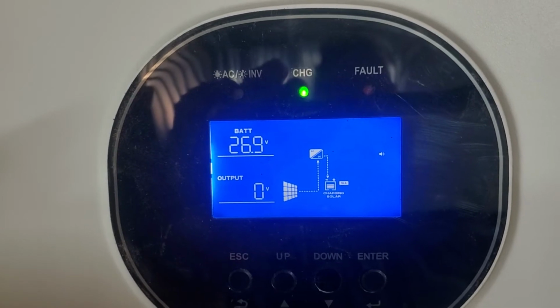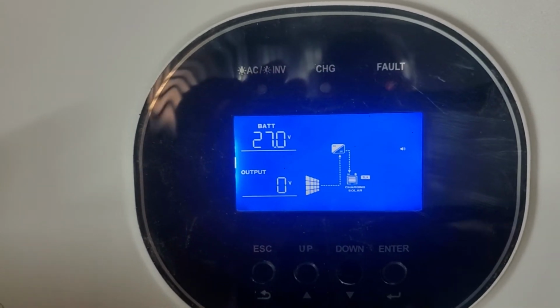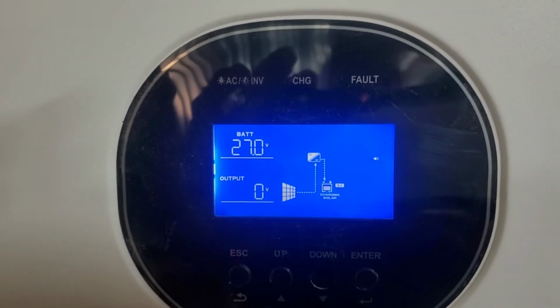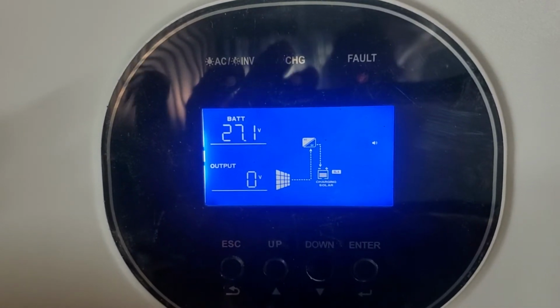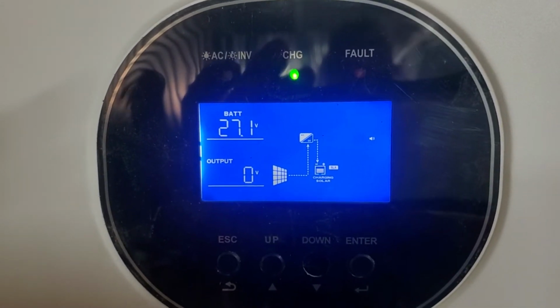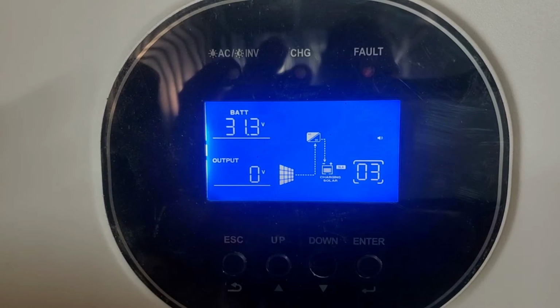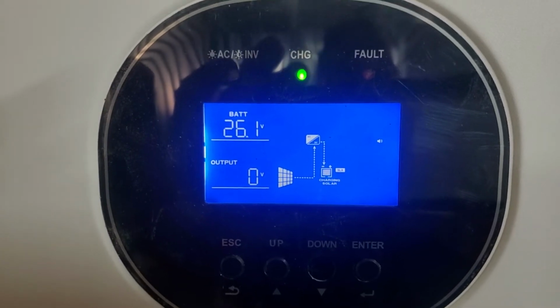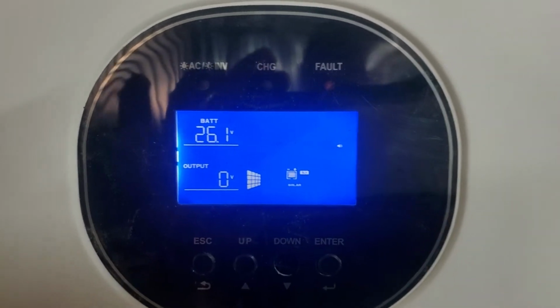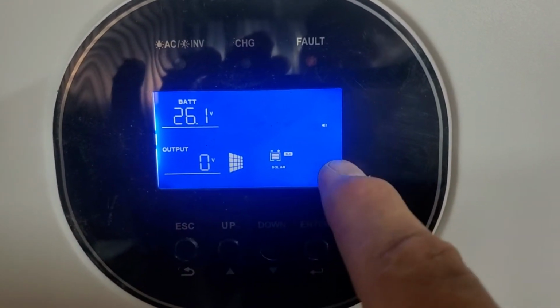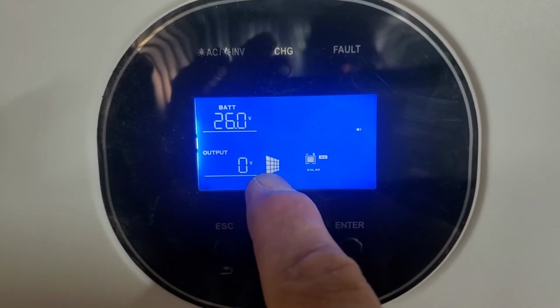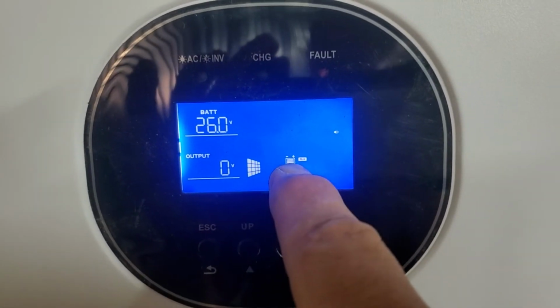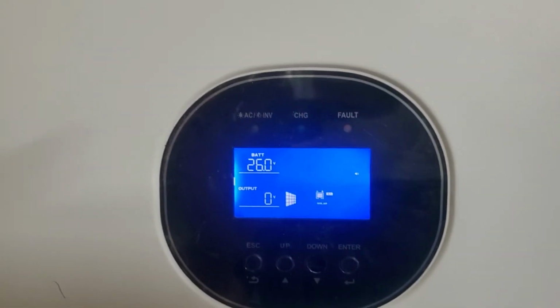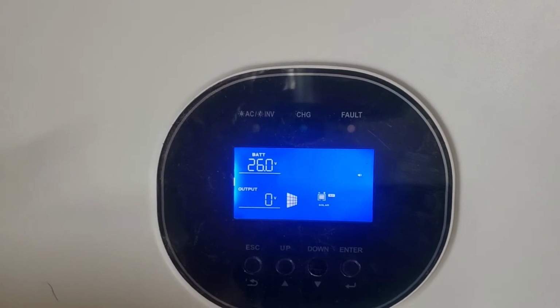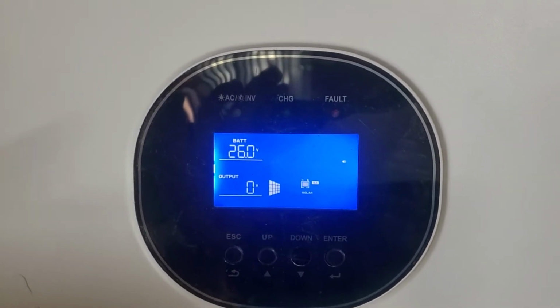Look there, you see 31 volts, it suddenly jumped to. Usually it might give you a fault 08, but now that solar panel will not charge that battery because it detected that there's something wrong. That battery went open circuit to 31 volts, you saw that.